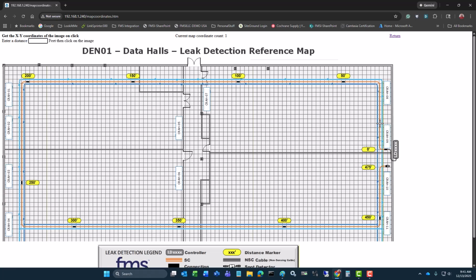Wait typically about 30 seconds, clear the leak, close it up, move to the next point, and just keep going through and marking. Then you can make a reference of, hey, I did my first mark at reference 1, reference 2, 3, whatever it may be. Go back to the leak detection controller and go through the alarm history, because you'll see those alarm counts and you'll be able to record that out if you don't have any mapping data already recorded for your system.